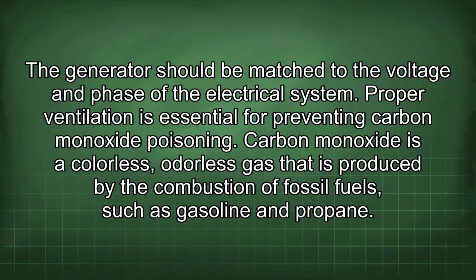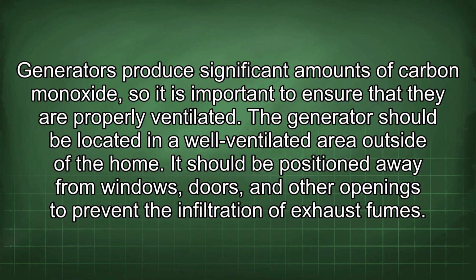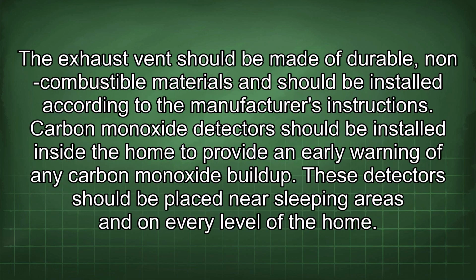Proper ventilation is essential for preventing carbon monoxide poisoning. Carbon monoxide is a colorless, odorless gas that is produced by the combustion of fossil fuels, such as gasoline and propane. Generators produce significant amounts of carbon monoxide, so it is important to ensure that they are properly ventilated. The generator should be located in a well-ventilated area outside of the home. It should be positioned away from windows, doors, and other openings to prevent the infiltration of exhaust fumes. The exhaust vent should be made of durable, non-combustible materials and should be installed according to the manufacturer's instructions.